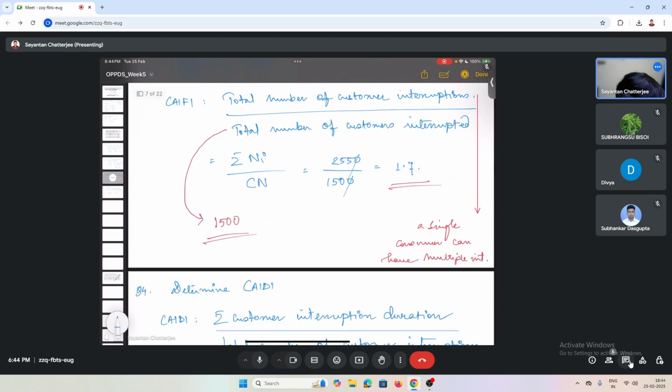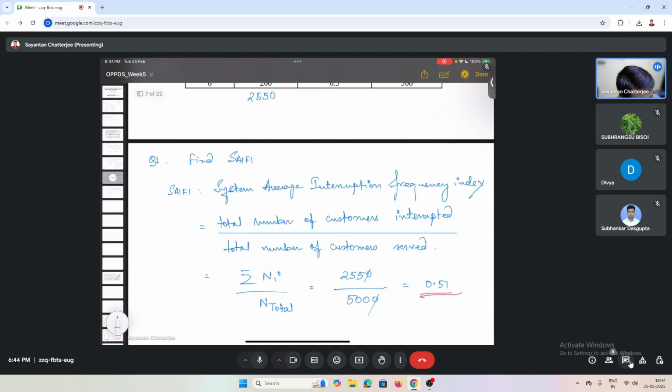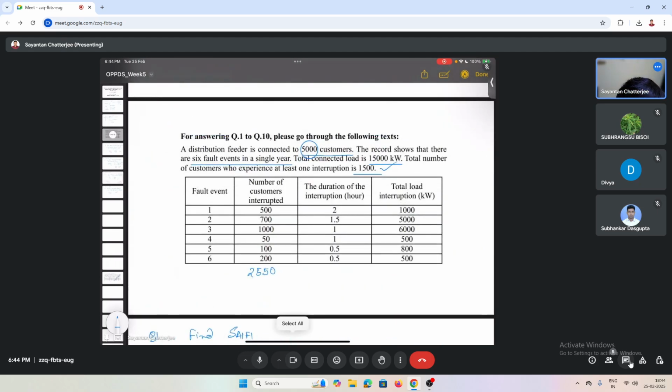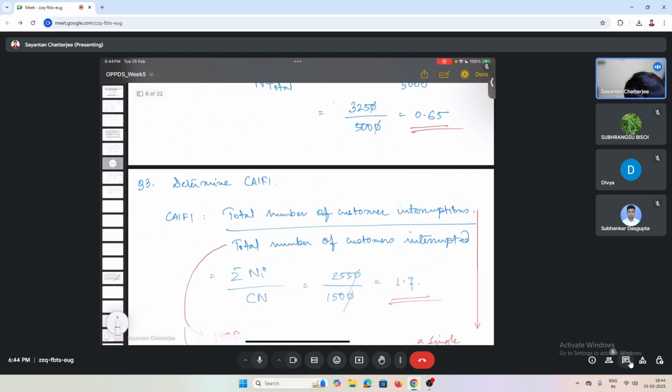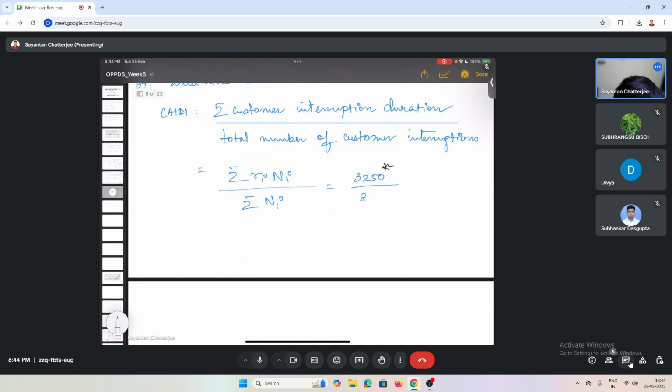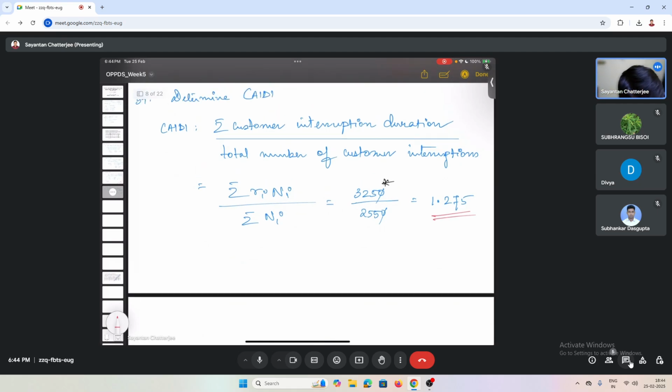And this is NI. So what is NI? Number of customers who got interrupted, the NI that we have calculated initially. So number of customers who got the interruptions, 2550. So this will be the final answer, 1.275. Just match the answers, right? If you have any doubts, we can also discuss, but if you don't, we can continue. But this is the answer of CAIDI, right?